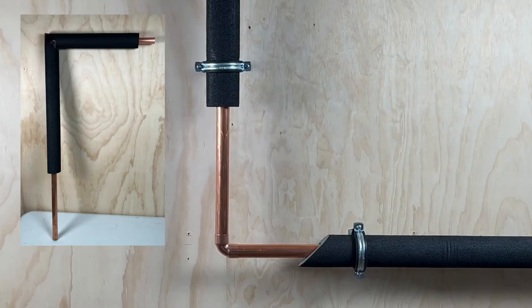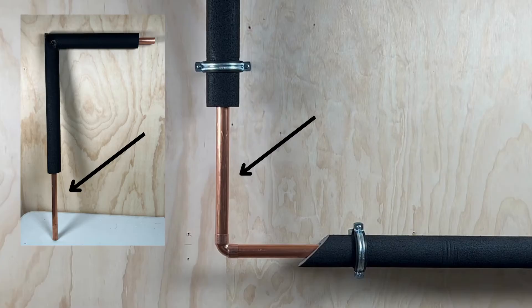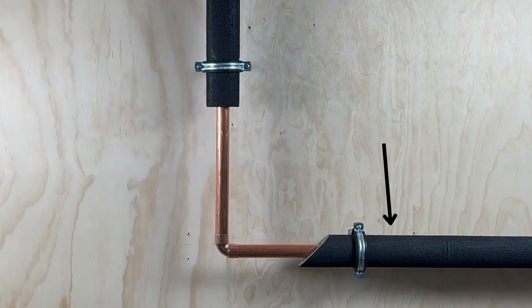The pre-made through the wall kits that we've made, you can make them elbowed up and all insulated pipes and sealed. We always leave a length of pipe showing without insulation - that's if you're sweating up or soldering the pipework, you need to keep the heat away from the insulation and then fit it. If it's going to be a press fit fitting, then that could be a lot shorter. As you see the part on the horizontal, that's a full length of insulation and that's got no cutting it whatsoever.